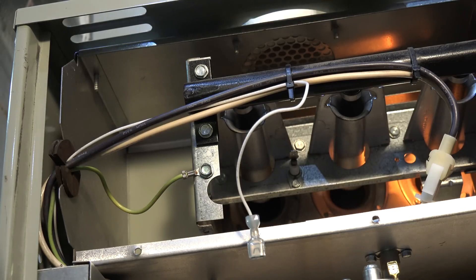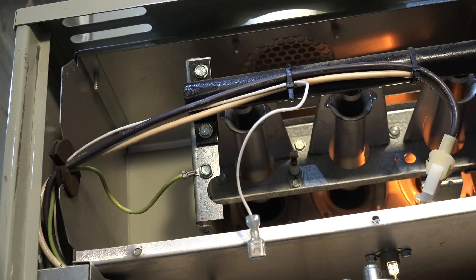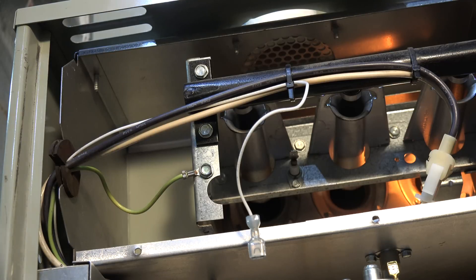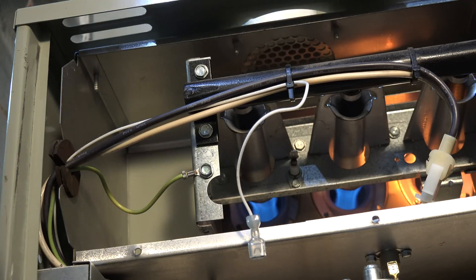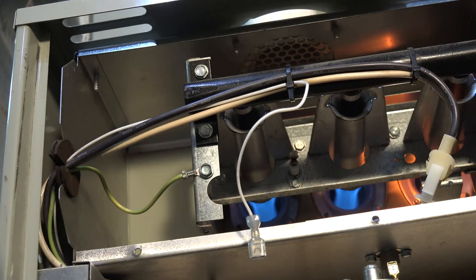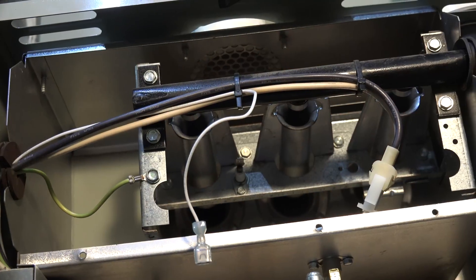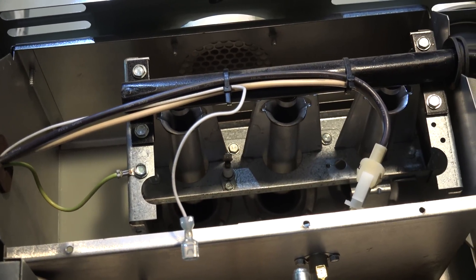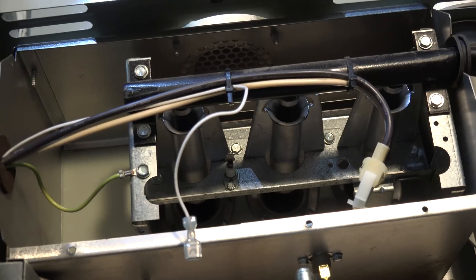Now I notice the hot surface igniter's coming on again and it's going to try to light again. Now it's going to do this three times and then you look in your little window down the bottom. See, it just tried to light again and because the flame rod wire's off, it's not going to light.